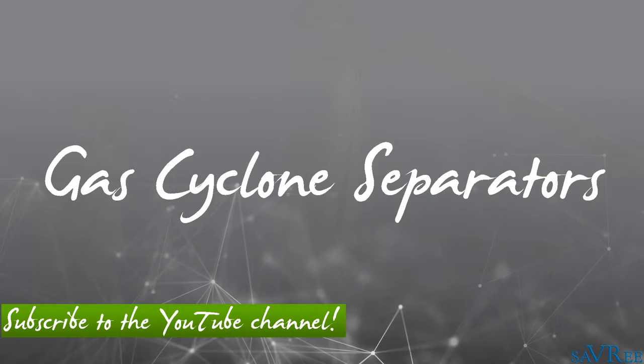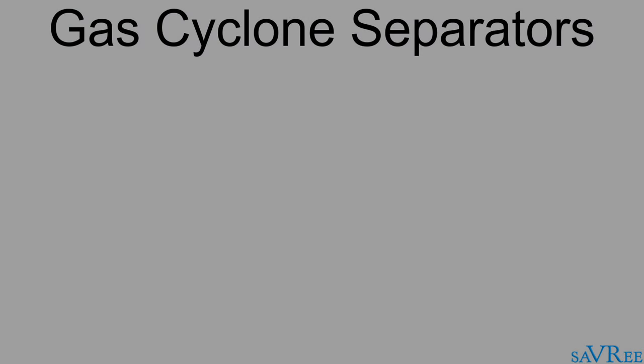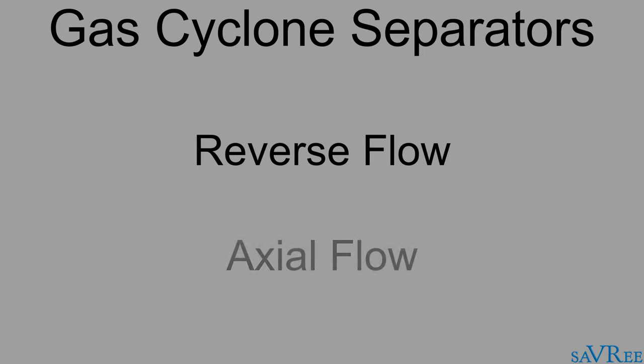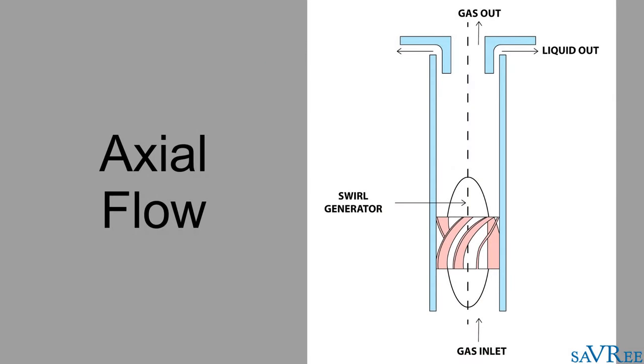Gas cyclone separators are grouped into two main categories: reverse flow and axial flow. Reverse flow cyclone separators are cone-shaped. Gas enters the top of the separator body, flows downwards, then flows back upwards, and is discharged. For axial flow cyclone separators, gas enters at one end and is discharged at the opposite end. The axial flow design is not as common as the reverse flow design.